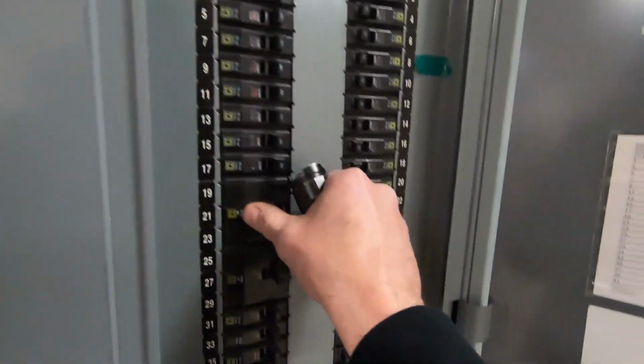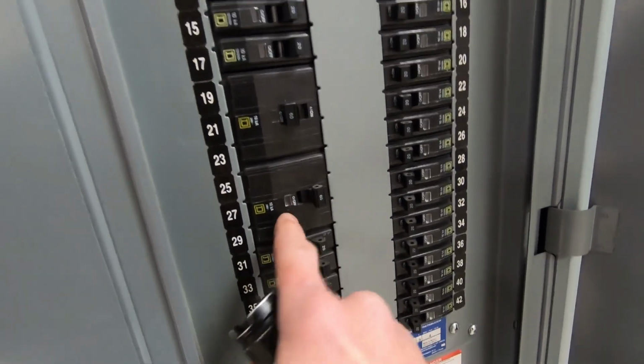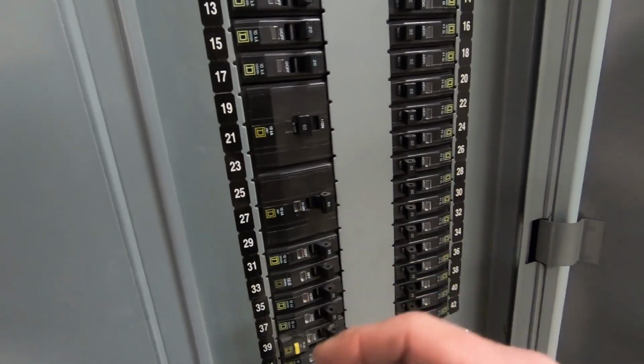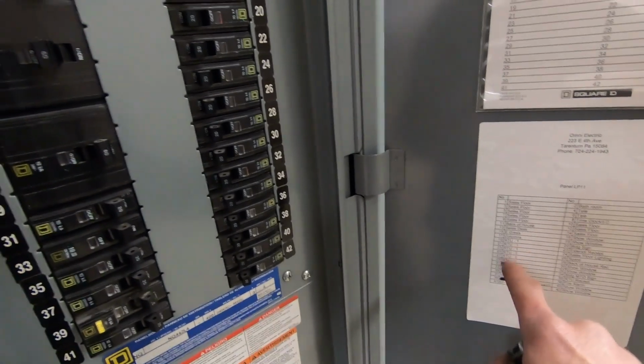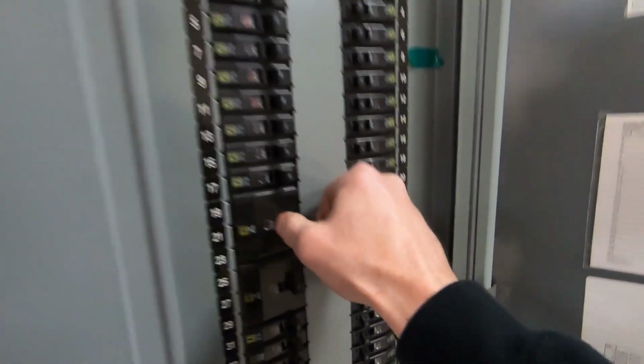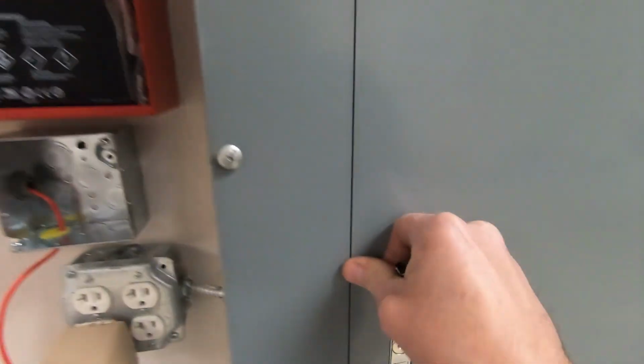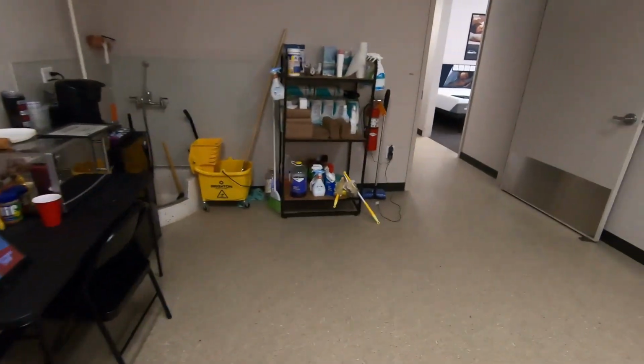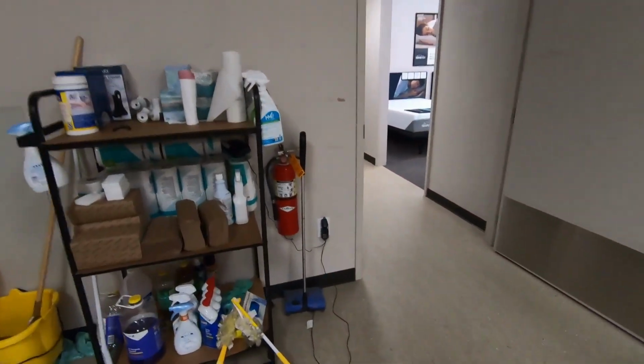It's just off. Let me go ahead. 19, 20, 23. That's this one. It wasn't tripped. This one's on. I think they flip-flopped them, possibly, you know, mislabeled. So power restored. Let's go cycle unit 2 on the roof, unit 1 in the breaker panel.